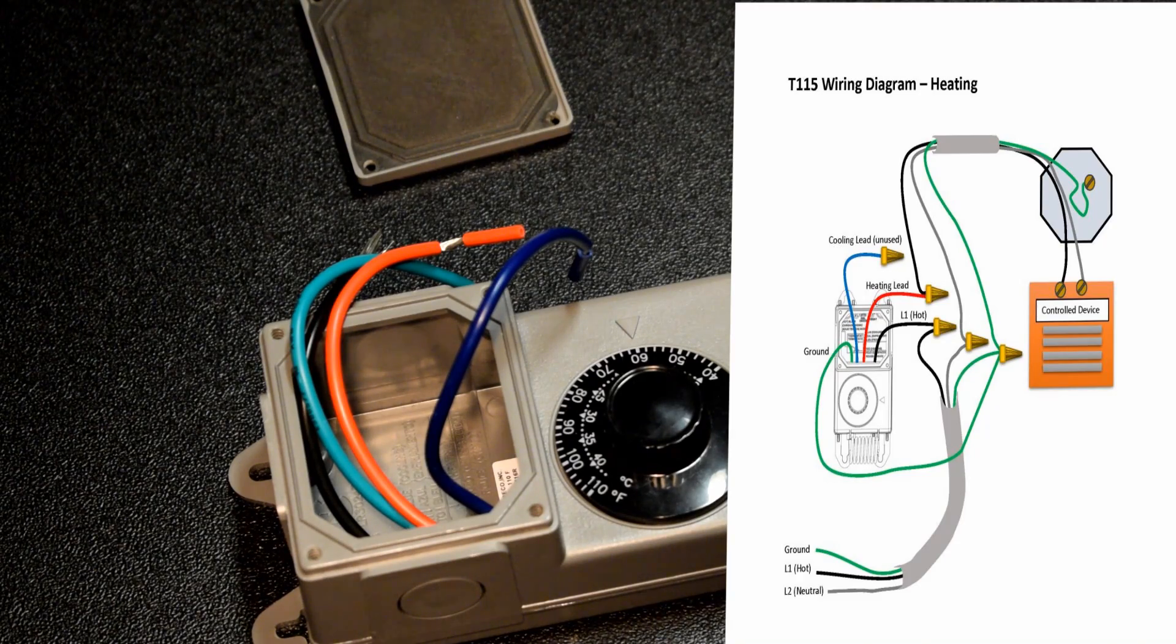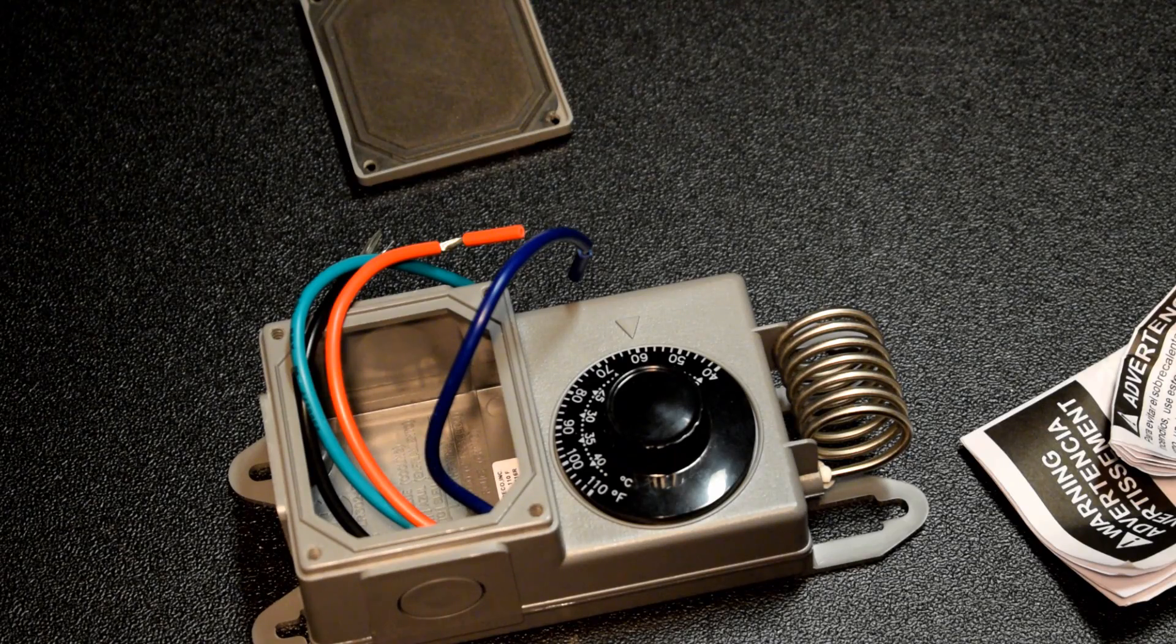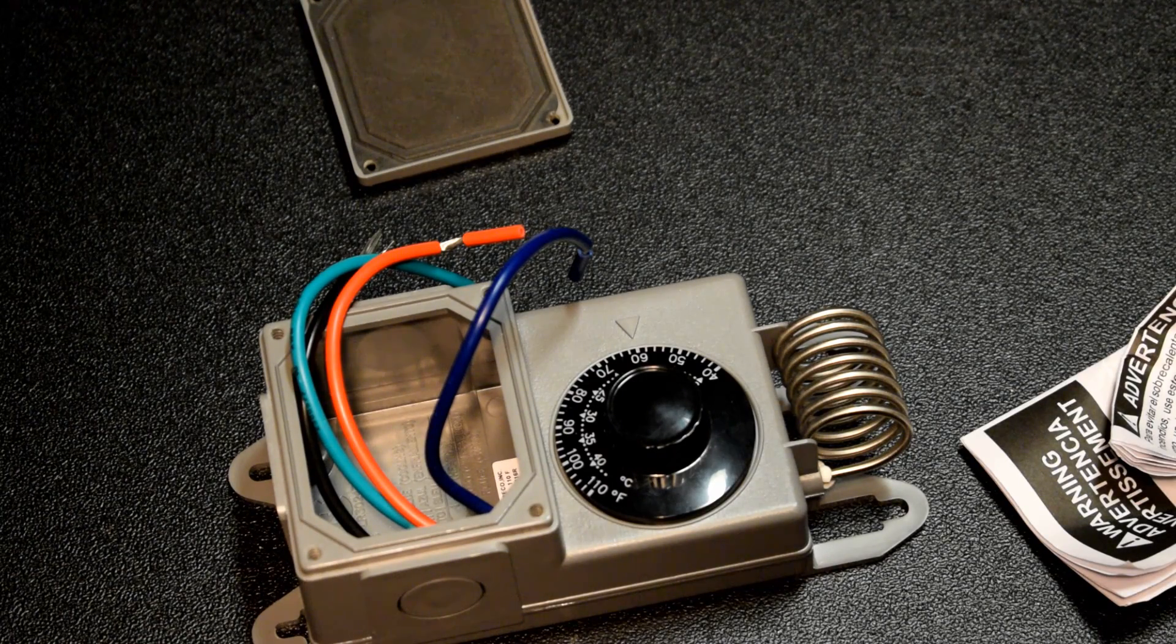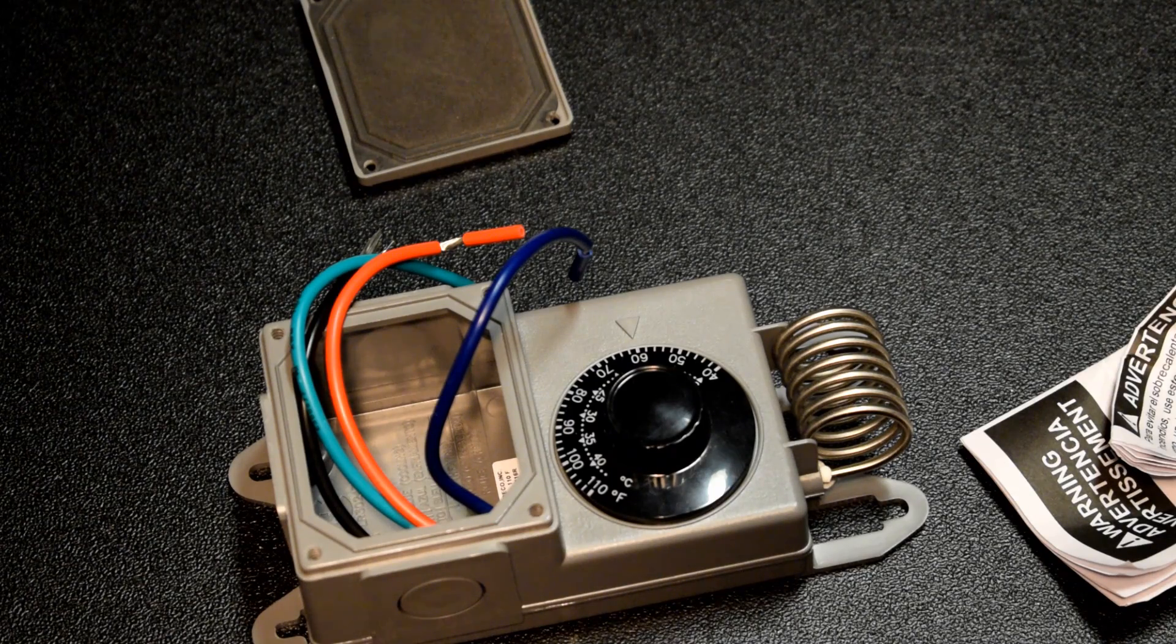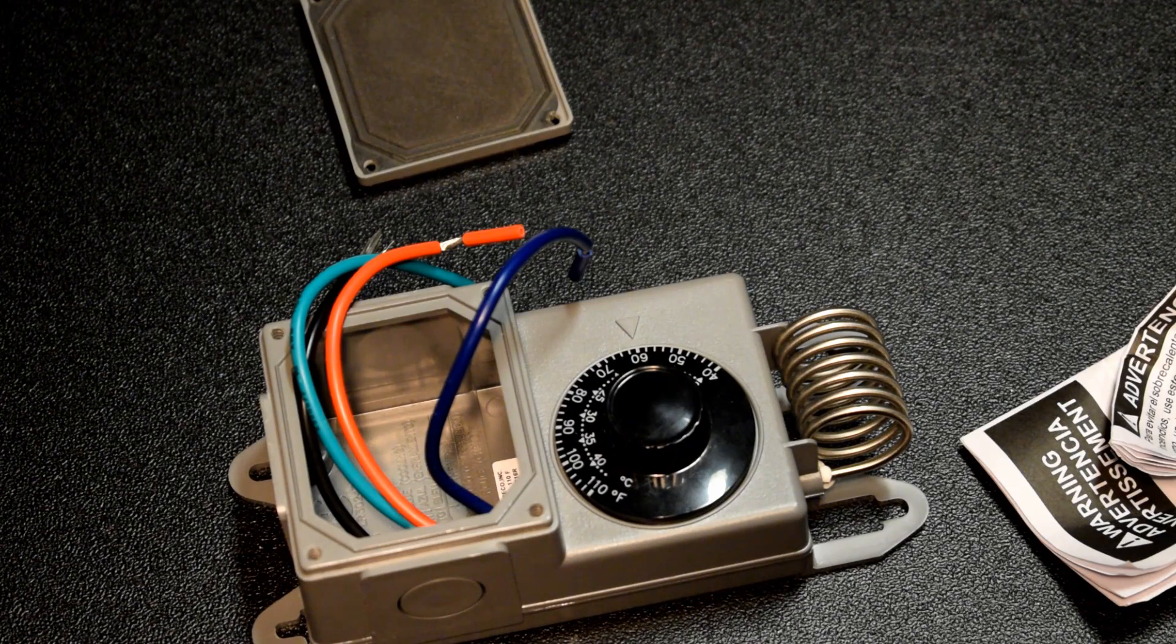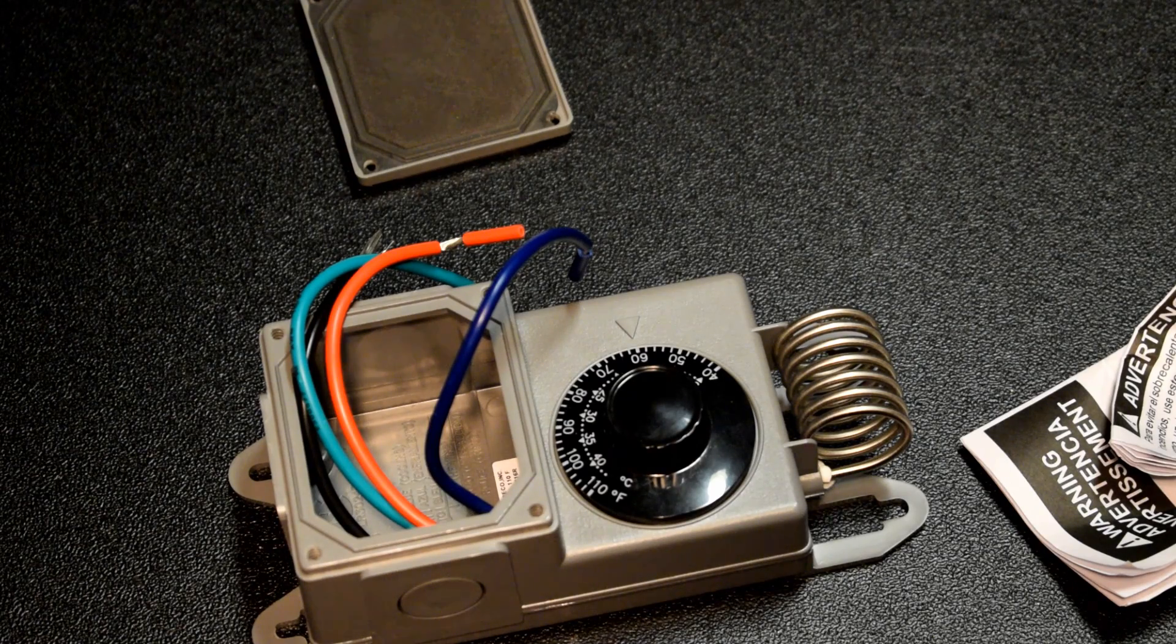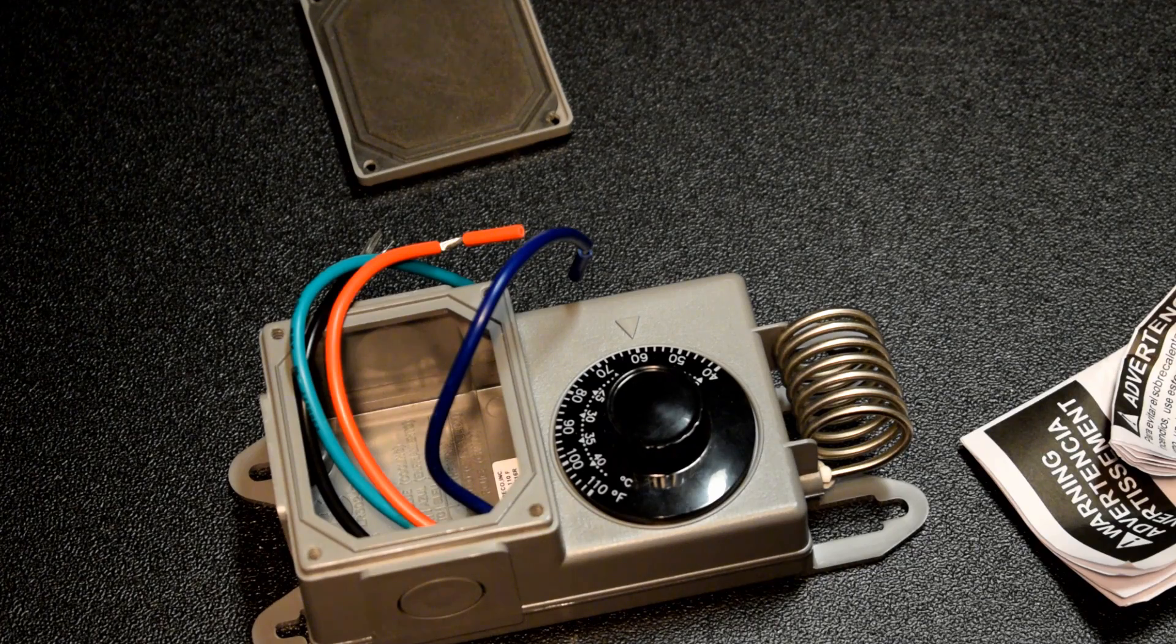Now, why can't I throw both a heater and a cooler on the same T115? That's a good question. Since it's a switch, there is no dead band in the T115 thermostat.